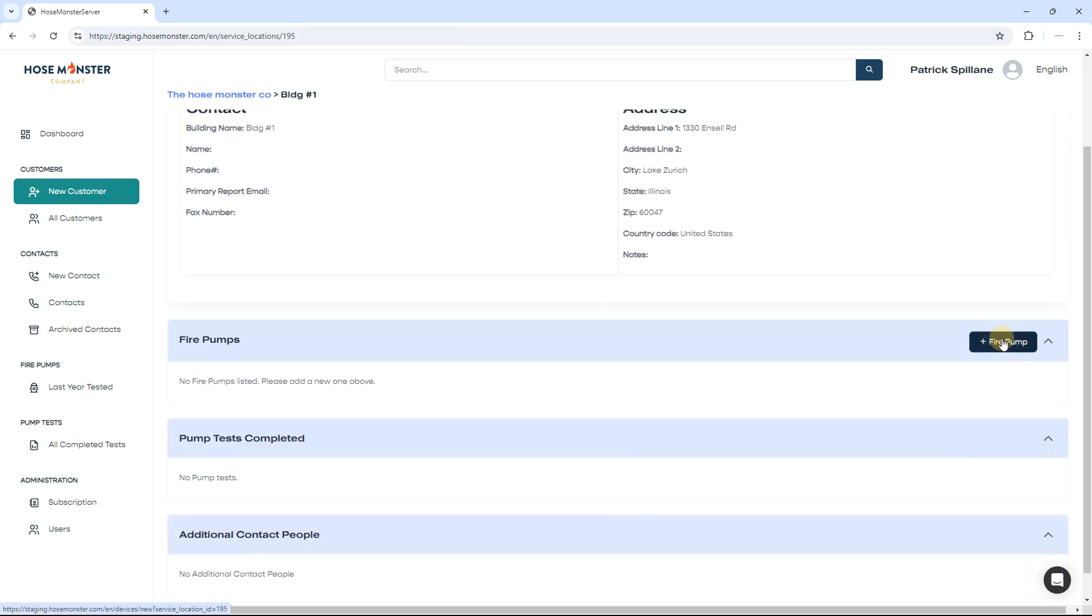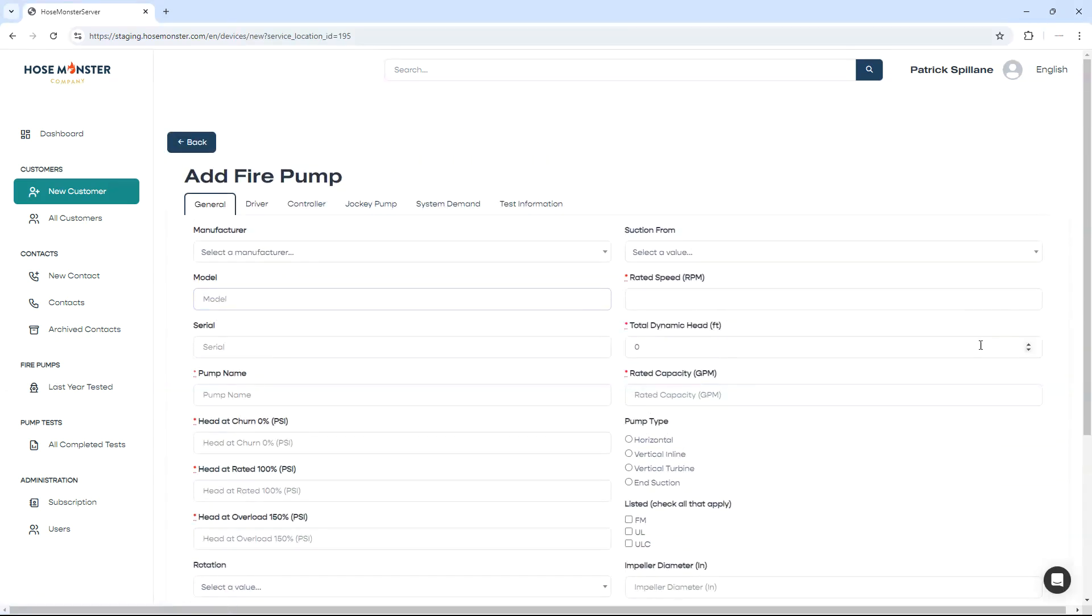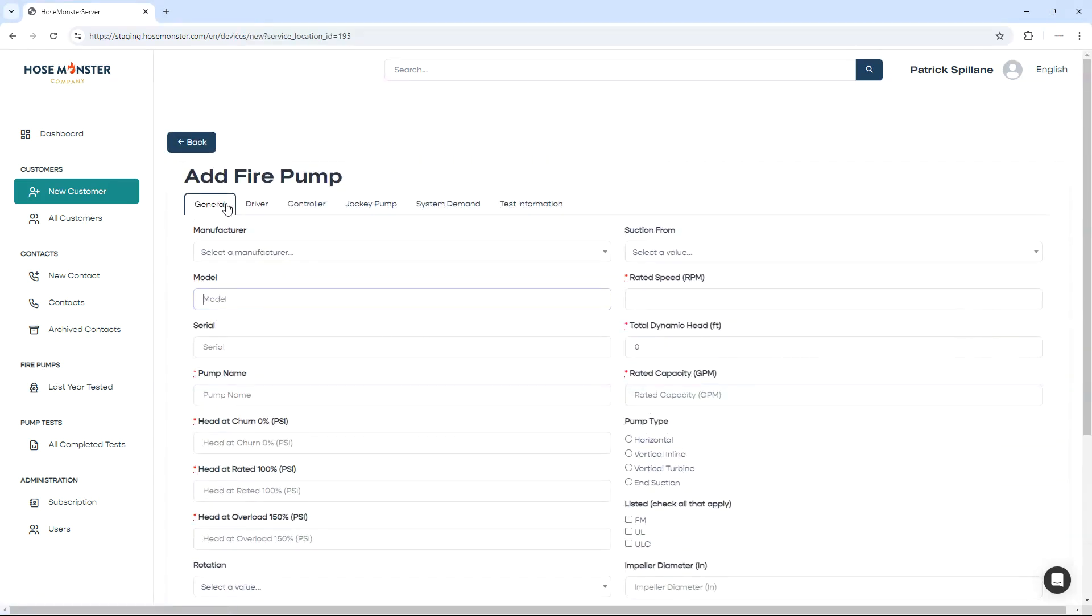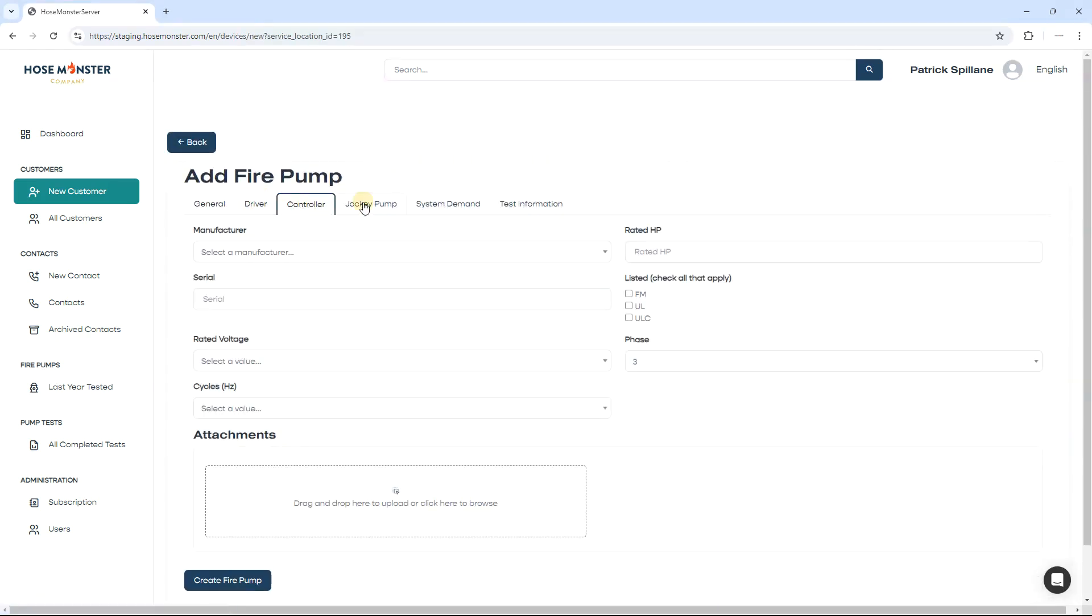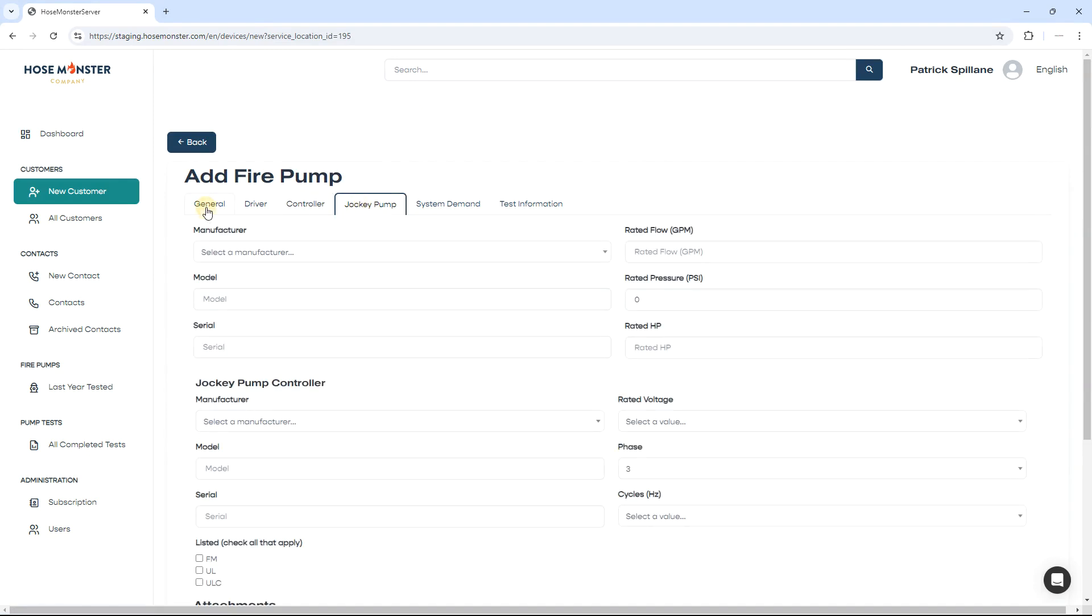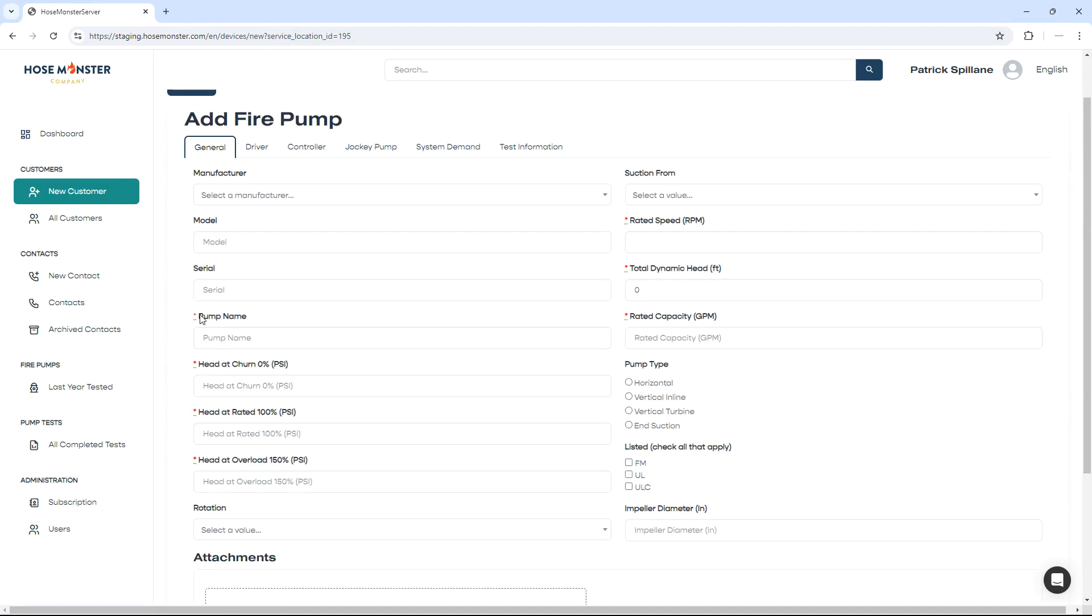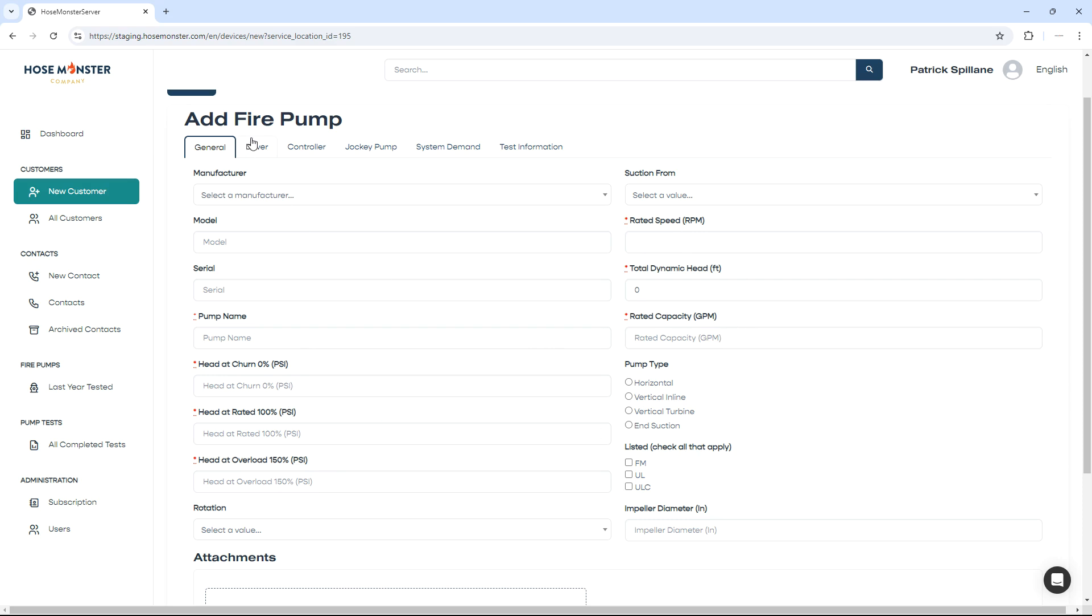Now we're ready to add our fire pump details. The fire pump information is split up into tabs for each component at the top of the page. Please note the red asterisk next to pump name, your head pressure ratings, the rated RPM, and the rated capacity of the fire pump is required for a fire pump to be created.